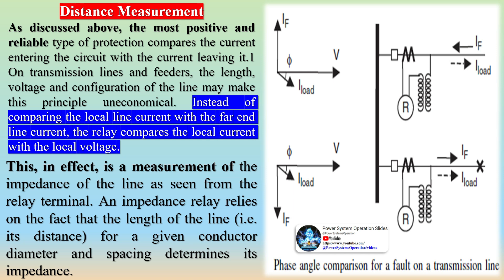These relationships are explained for two transmission lines in figure. This difference in phase relationships created by a fault is exploited by making relays which respond to phase angle differences between two input quantities such as the fault voltage and the fault current in the present example.